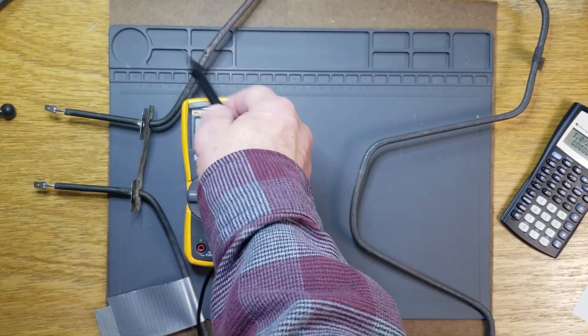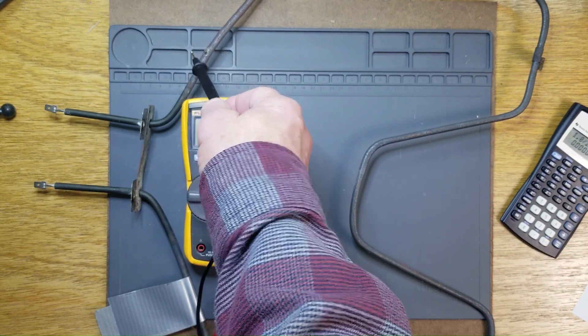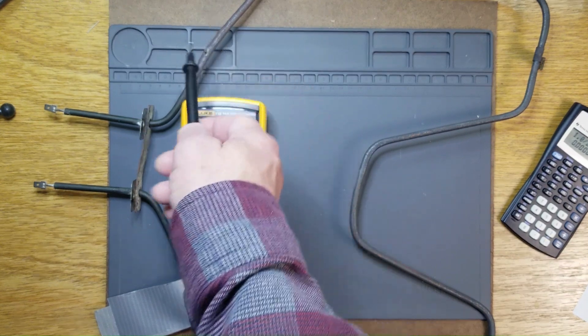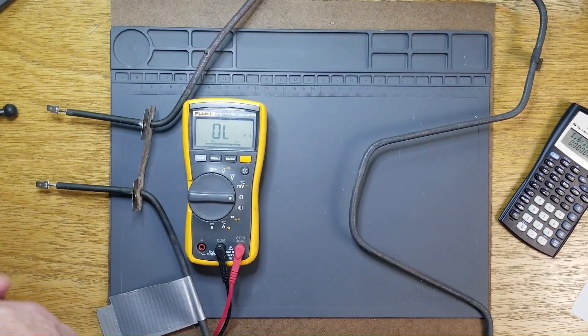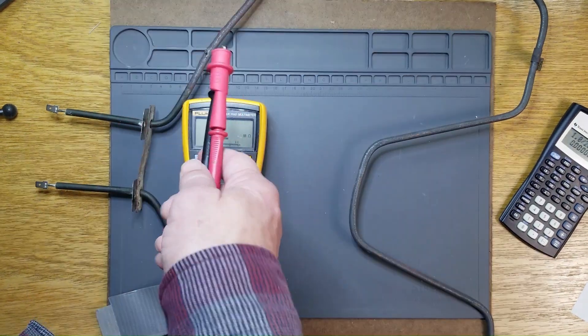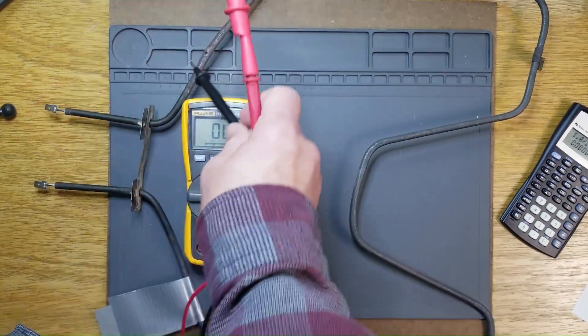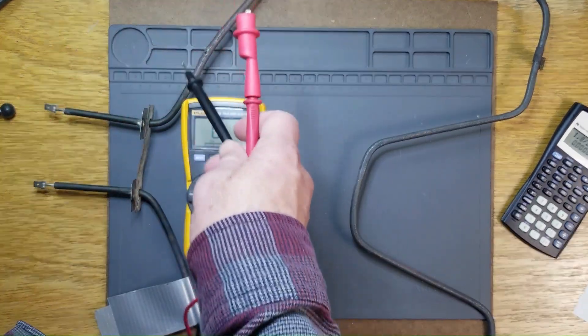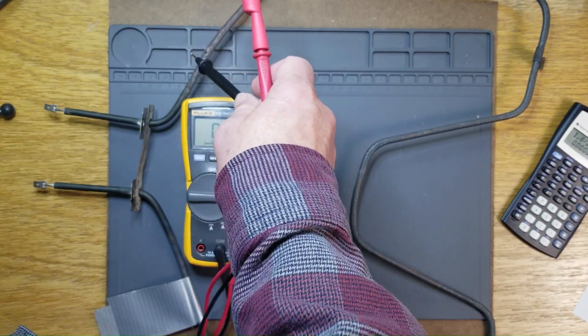the effective resistance, if it tripped at 30 amps minimum, the effective resistance would have been about 4 ohms between here and the outside of this element.